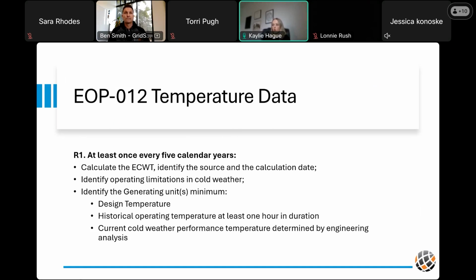A very extreme cold weather event could change your limitations and the historical data impacting your ECWT. So R1 also requires that at least once every 5 calendar years you are calculating that ECWT, meaning identifying the source of your data and capturing the date you calculated it.